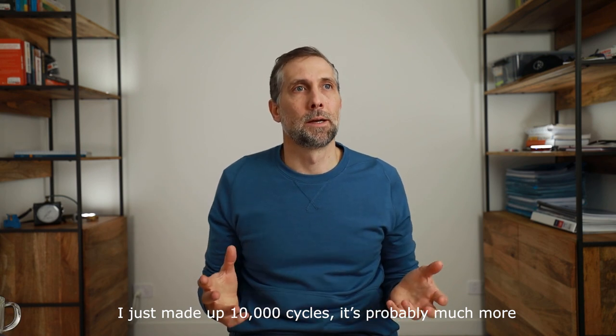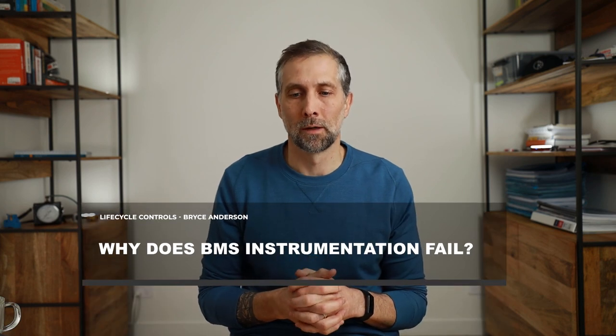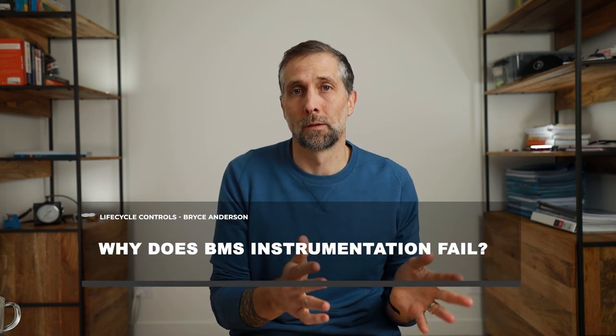So the idea here is if we can halve the amount of time that the actuator goes up and down, if we can halve the amount of movement every day, it would probably result in that actuator lasting for double the amount of time. So rather than failing at 10 years, it'll fail at 20 years. That's the idea. Some of you might be getting an idea of where I'm going with this. This is PID loop tuning.